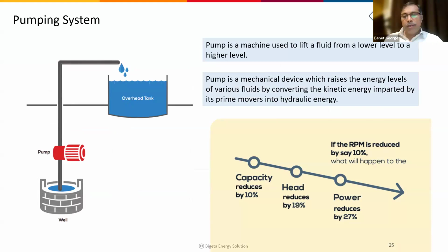Then one thing we have to remember is the affinity law based on the speed. In case the pump has a variable frequency drive, it varies the speed of the pump to reduce the capacity, based on variable demand applications. So when you reduce the speed by 10%, head reduces by 19% and power reduces by 27%. So we'll see some of the opportunities to install a variable frequency drive.